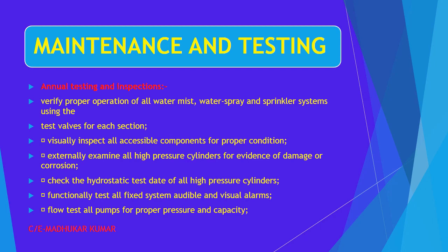Externally examine all high pressure cylinders for evidence of damage or corrosion. Okay, so if at all any high pressure vessels which we have seen, we have to maintain the pressure at 8 bar, so that has to be visually examined. Check that the hydrostatic test date for all high pressure cylinders has to be maintained. Functionally test all fixed audible and visual alarm systems. Okay. Flow test of the pumps for the proper pressure and capacity.